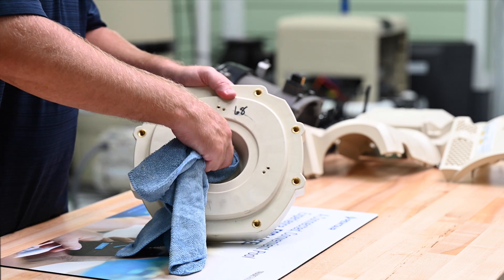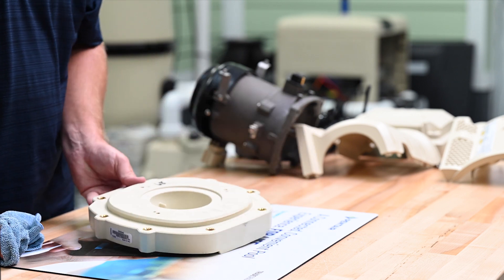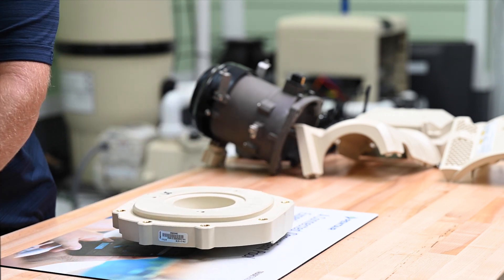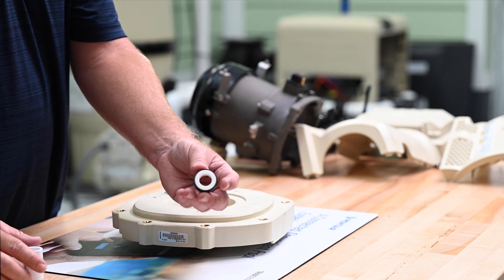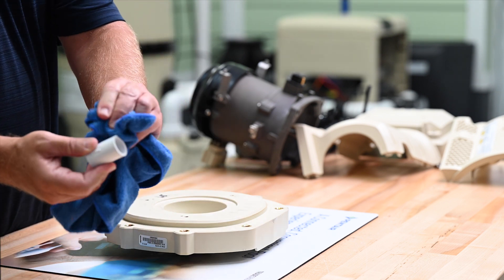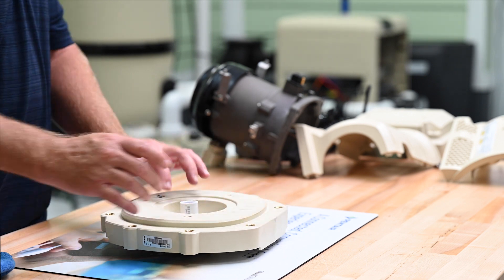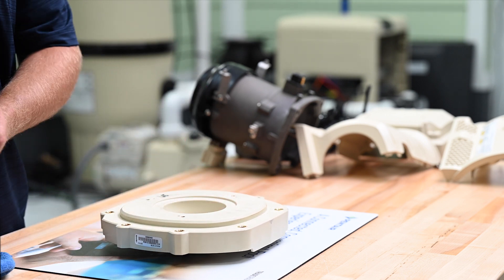Now we'll begin putting the pump back together by first installing the new seal. Let's first make sure the seat is clean. Then we'll spray the seat with a solution of soap and water or alcohol and water to help the seating process. When handling the seal, avoid touching the sealing surface to prevent contaminating the seal, which could lead to premature failure. Now we'll use a clean 1.5" PVC coupling to press the seal into the seat. We can usually press the seal in by hand, but if needed, we can use a rubber hammer to help seat the seal.